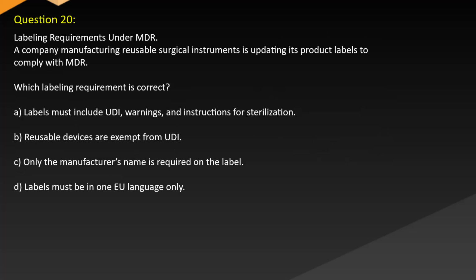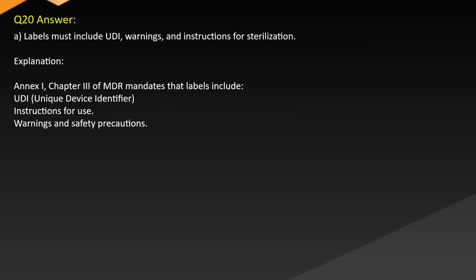Question 20. Labeling requirements under MDR. A company manufacturing reusable surgical instruments is updating its product labels to comply with MDR. Which labeling requirement is correct? A. Labels must include UDI, warnings and instructions for sterilization. B. Reusable devices are exempt from UDI. C. Only the manufacturer's name is required on the label. D. Labels must be in an EU language only. Answer: A. Explanation: Annex I, Chapter III of MDR mandates that labels include UDI, unique device identifier, instructions for use, warnings, and safety precautions.